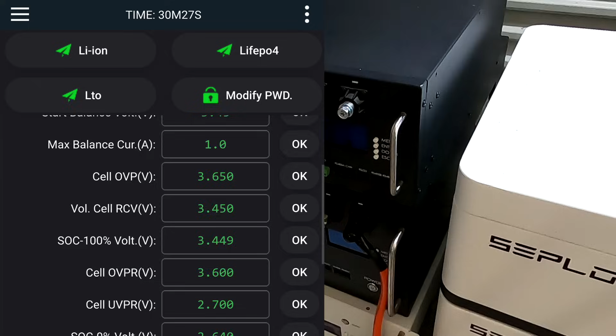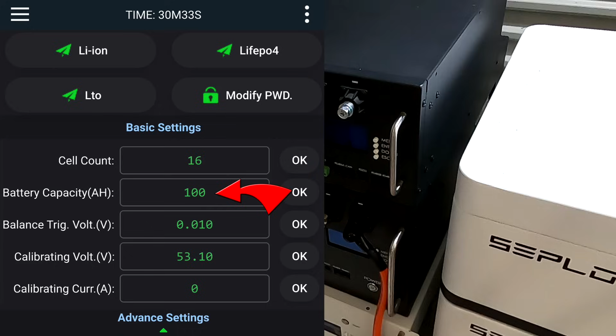Alright, back in the mobile app, let's go into settings. I have already changed the settings as I would set them in a productive environment: 16 cells, 100 ampere hours, 10 millivolt deviation, start balancing at 3.45, cell OVP 3.65, and the requested charge voltage, which is your bulk or absorption voltage, is 3.45.